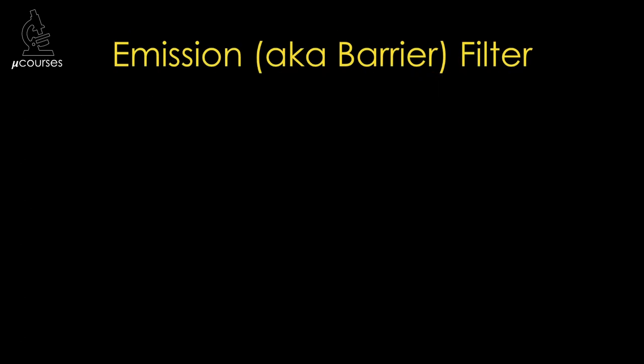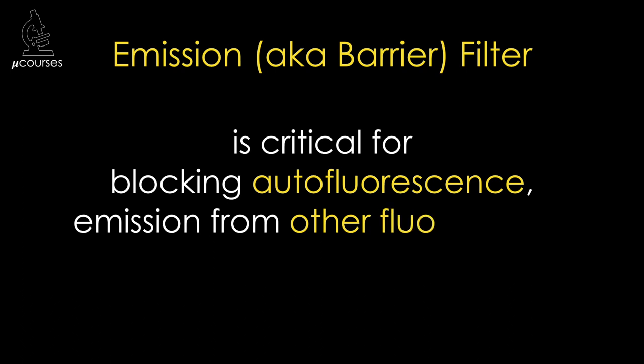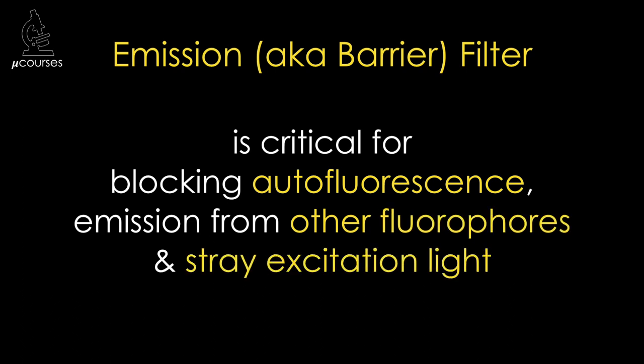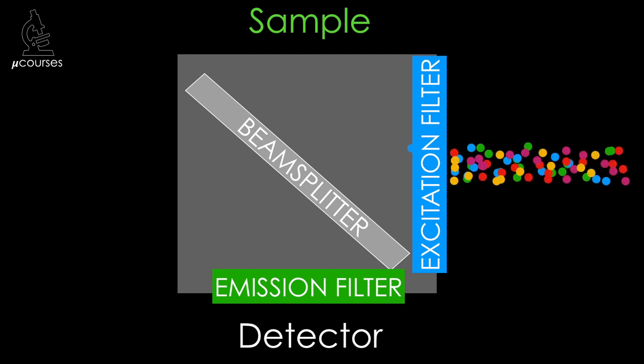Now let's consider the emission light. The dichroic mirror allows the majority of the emission light to pass through. In principle we could stop here, but it's best to add an emission filter. The emission filter should select for the emission wavelengths expected from the fluorophore. Emission filters play a critical role in blocking autofluorescence, emission from other fluorophores, and stray excitation light. The dichroic beam splitter isn't perfect and allows some excitation photons through; the emission filter blocks these stray photons, resulting in lower background and higher contrast images.